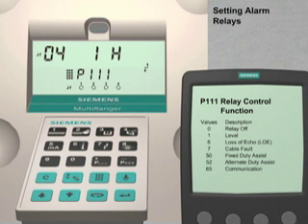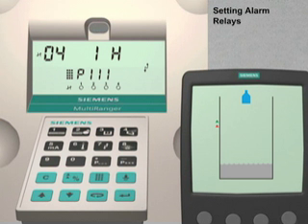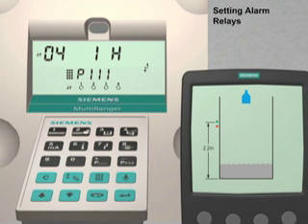We will now program the on and off set points for our high level alarm. For a high level alarm, the on set point has to be a higher value than the off set point. This will ensure that the high level alarm is triggered when the liquid level rises above the on set point and turns off when the liquid level drops below the off set point. In our application, we will configure the high level alarm to come on when the liquid level rises above 2.2 meters and turn off when the liquid level drops below 2 meters.